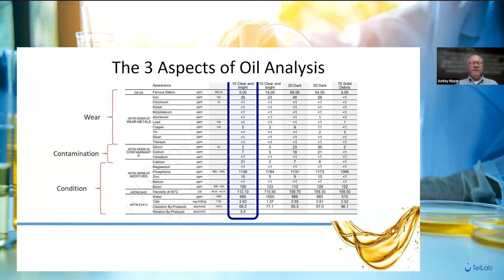If you look at an oil analysis report, most laboratories loosely group the tests into these three areas: machine wear at the top, contamination in the middle, and lubricant condition at the end. When we get to the different maintenance philosophies we're going to discuss now, they will direct you to whether you should be concentrating on wear metals, contamination, or condition of the report. Before we get into the different maintenance philosophies, I just want to talk briefly about types of failure.